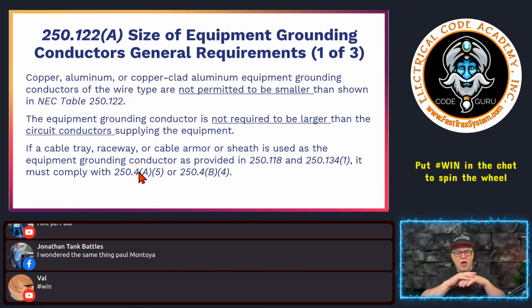Okay, so the B4 is dealing with the ungrounded systems, and A5 is dealing with grounded systems. So we have to make sure we make all the connections, create a low impedance effective ground fault current path, make sure we connect everything together properly in order to facilitate the operation of an overcurrent protective device. We have to do all the connections properly. That's what we have to do, okay? And it's important with things like cable trays, if your cable tray is actually listed for grounding and bonding, that you make sure the joints and segments are connected properly. If they're not, you have a properly sized bonding jumper, all that kind of thing. With raceways, make sure you tighten your fittings tight, make sure you use listed fittings, all those type of things, okay? That's all it's reiterating, okay?